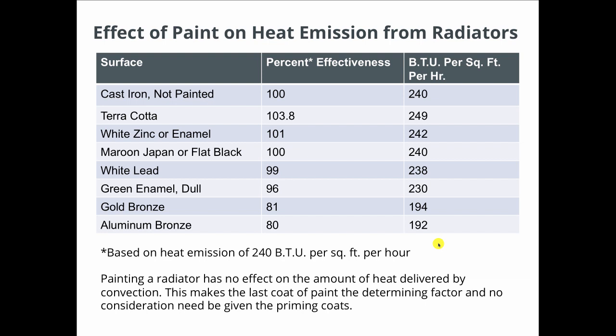If you paint it above, on top of that, say if you painted it black, it would go back to being 240 BTUs. If you painted it terracotta, which is the color of a flower pot, it would actually pick up 3.8%. You'd have more output. So the color of a radiator does indeed matter.